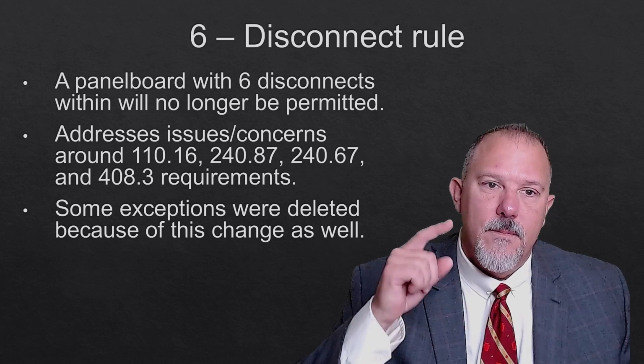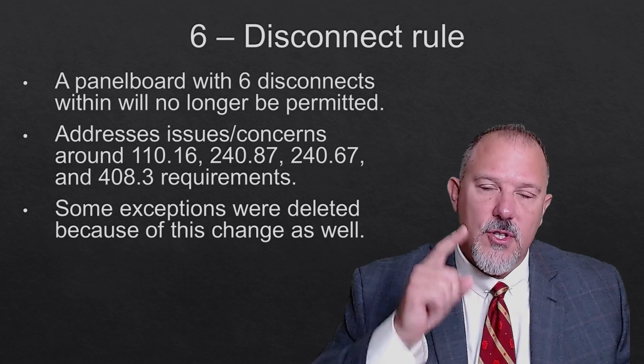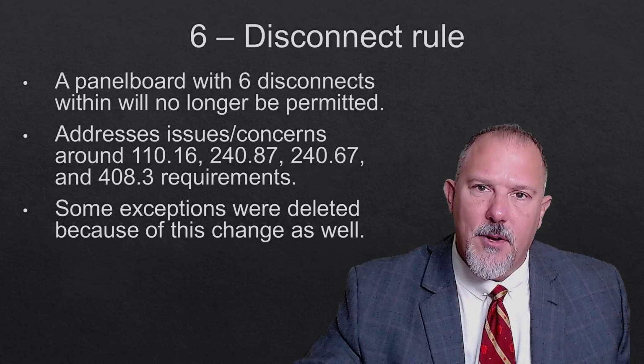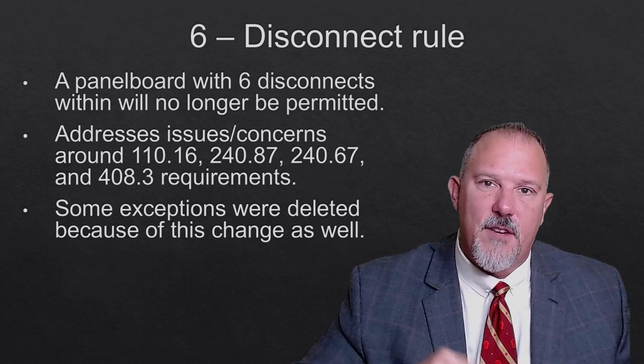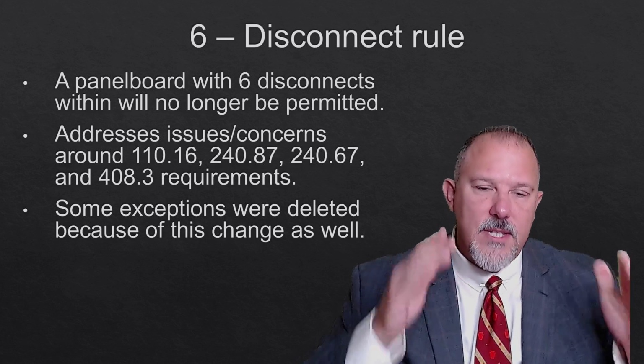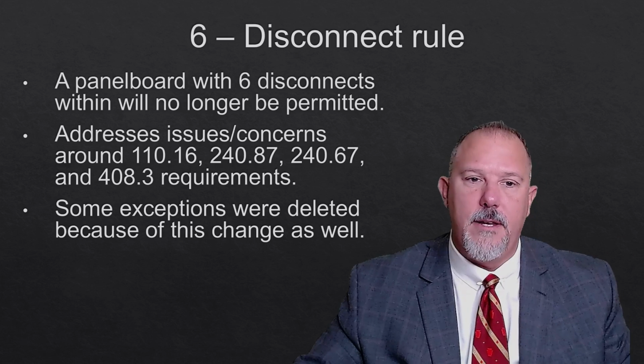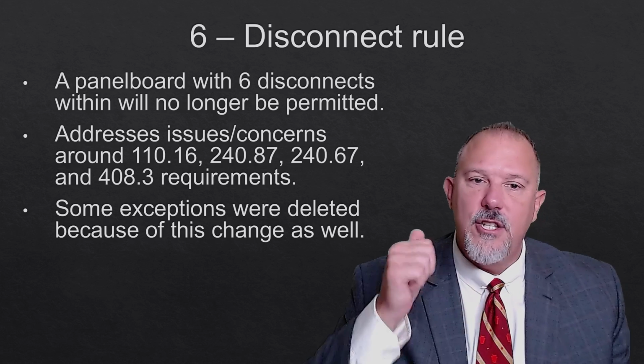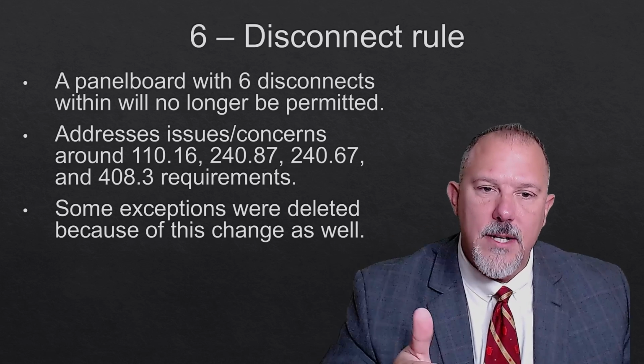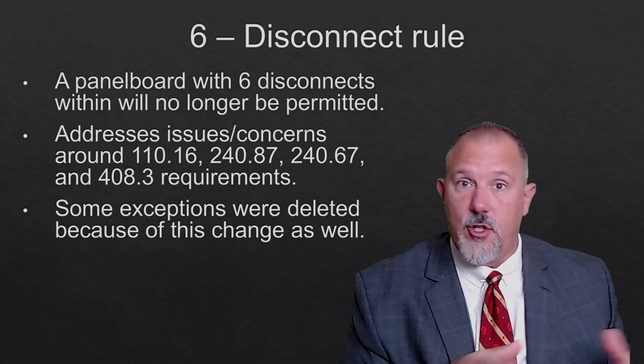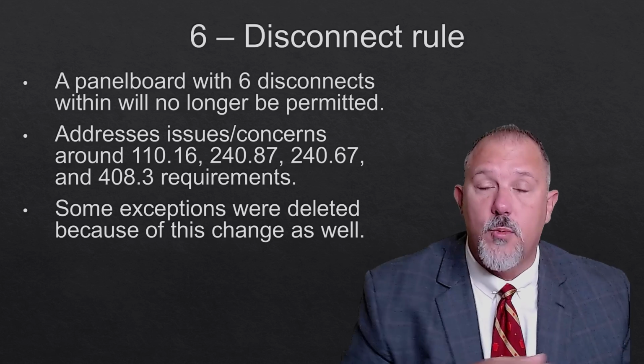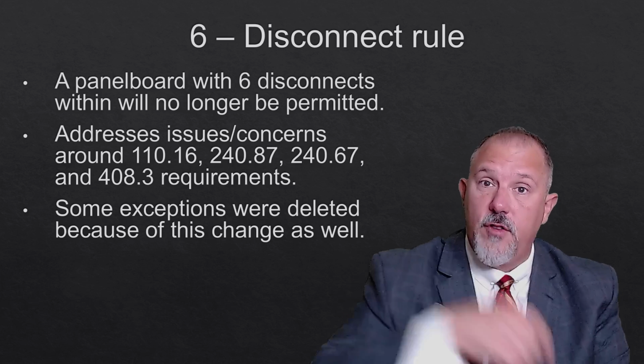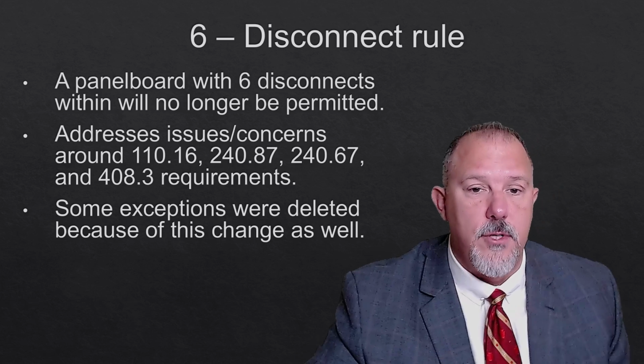So the 6 disconnect rule started to get questioned. And when we had the barrier requirements, the 6 disconnect rule came under fire again. Panel board with 6 disconnects is no longer permitted. And again, 110.16, 240.87, 240.67, and 408.3 is what drove those. And that's when the barrier requirements were in 408. But then we moved those to 230, and we're going to talk about those.